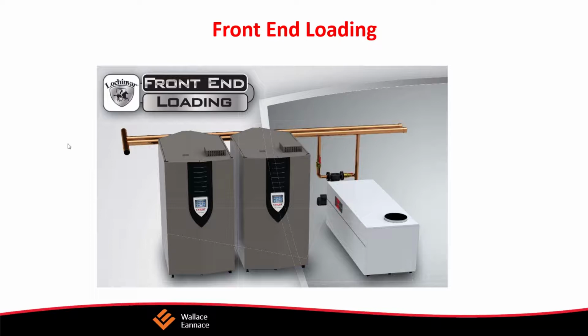And the concept is that if you look at baseboard, for example, as you can see, at 180-degree water, which is typically what we heat hydronic heating systems at, it would put out 570 BTUs per linear foot. If we had 130-degree water, or 140-degree water, it would produce about half as much. So if we cut the water temperature down, we've effectively reduced the output by 50%.